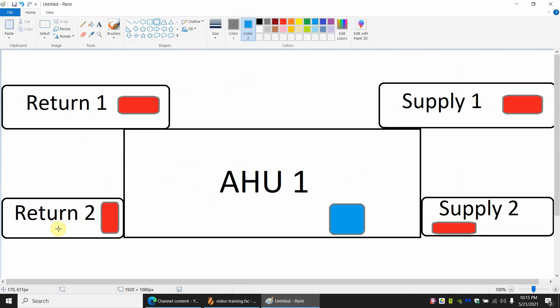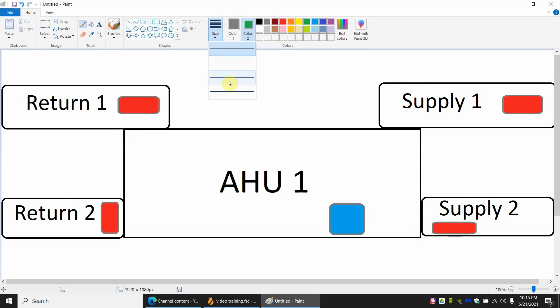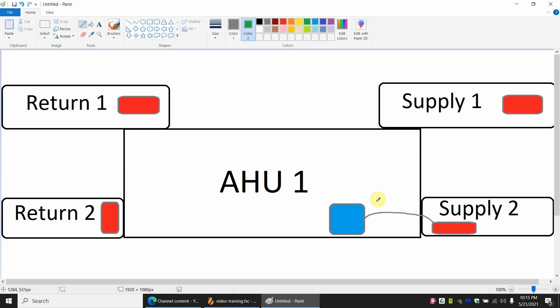So what that means is, if it's really easy to run the shutdown wire from supply two to the shutdown box, that's all the shutdown wire you need to run. So I'm just going to draw a really crude picture here. We're just going to run the shutdown wire from here to here, knowing that any four of these duct detectors, if they initiate an alarm sequence, this relay will trip and shut down the air handler. Saving you frustrating time figuring out how to run wires and how to wire up multiple relays together. Just pick the closest one. Do it through programming. So see you soon.